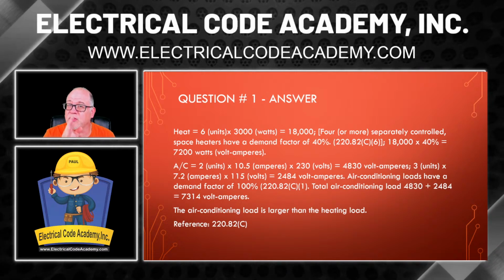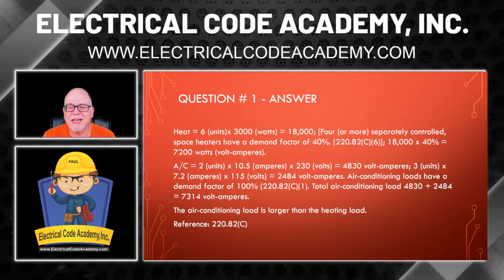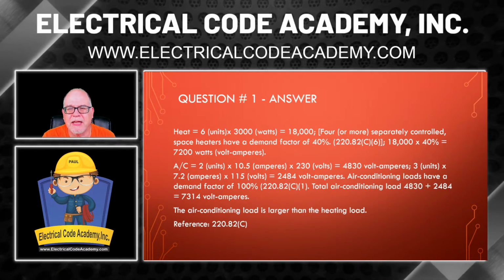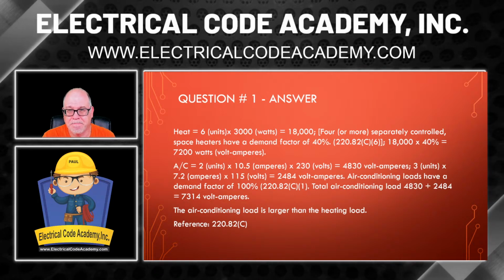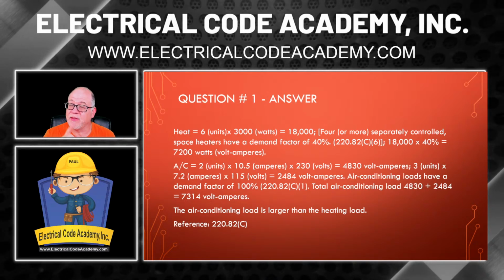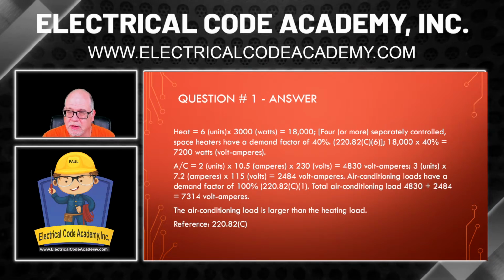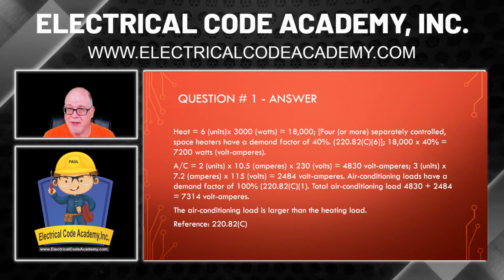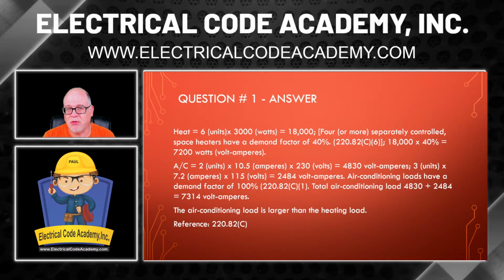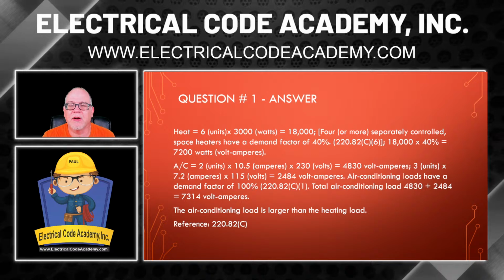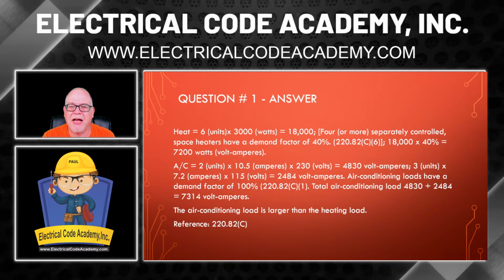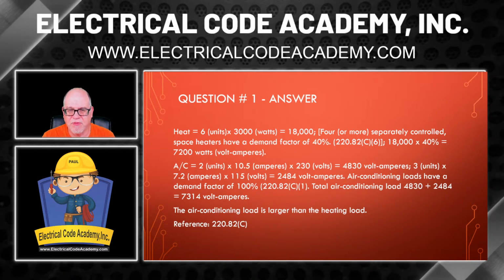Remember, use the voltage that's given in the question. That's going to give us 4,830 VA. Now let's do the 3 7.2 amp air conditioning units. That would be 3 times 7.2 times 115 volts. That is 2,484 volt amperes.